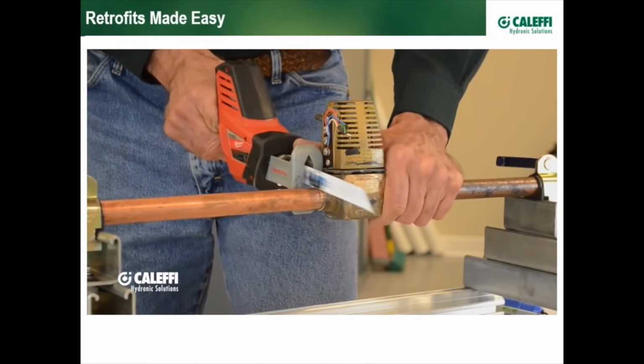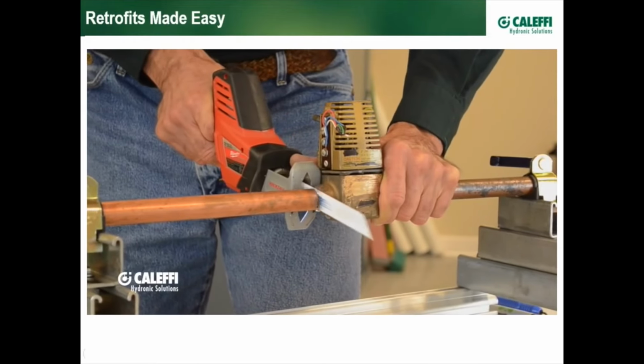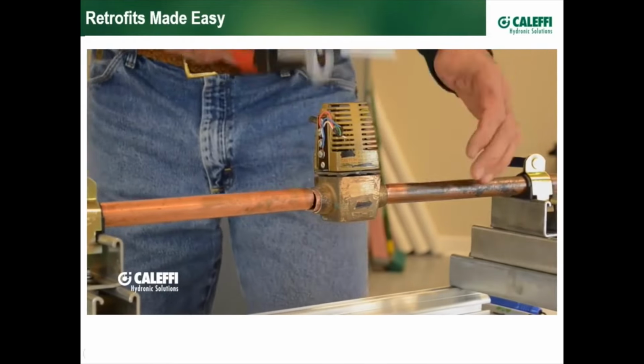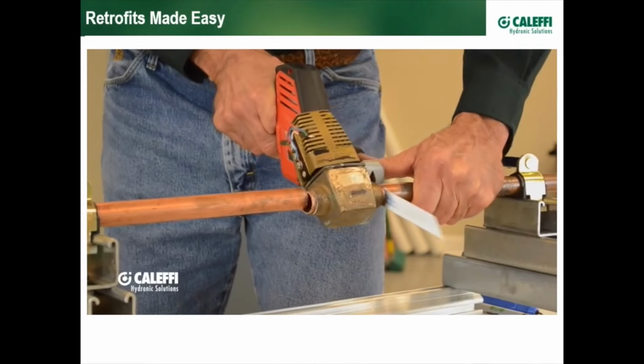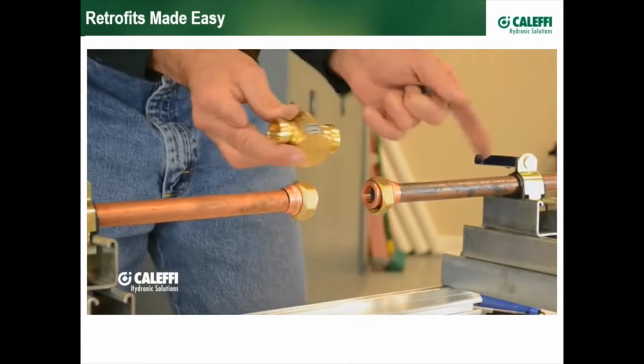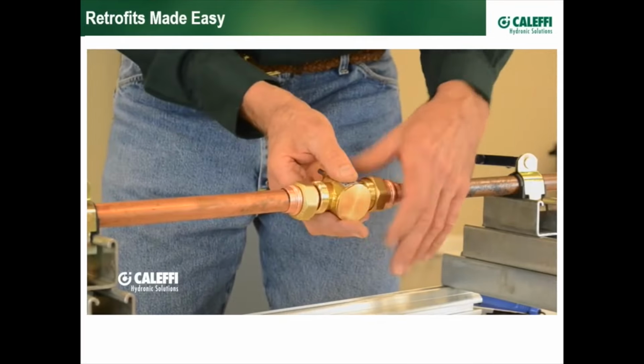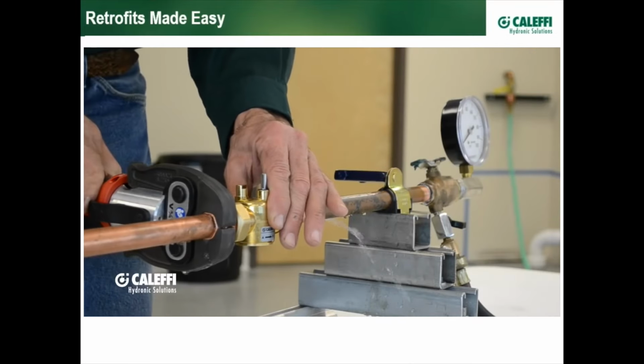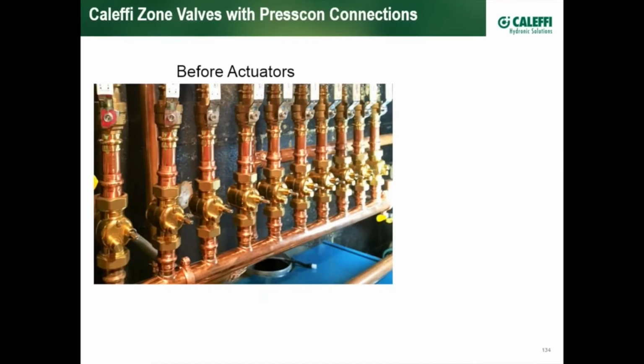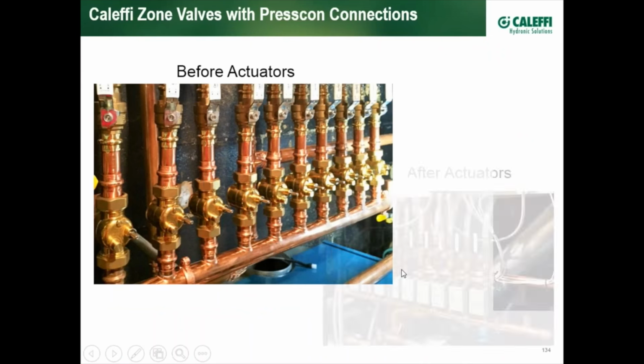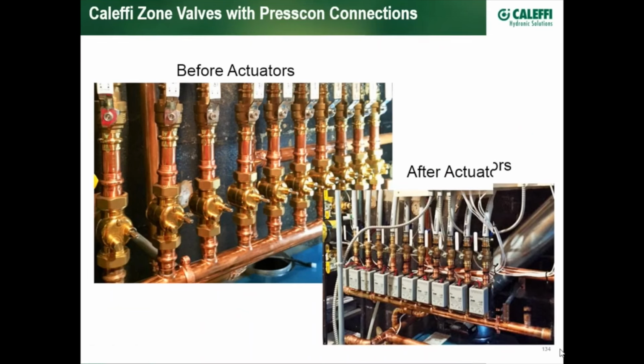They're great for when you're tired of replacing some valve's actuator and decide to go ahead and just replace the valve itself, cut it out and simply replace it with a Caleffi valve, and within minutes, as Bob is showing here, press it on, and now you have a highly reliable valve in place. Several of them here in this photograph before the actuators are placed on. You can see the press fittings and after the actuators have been installed.